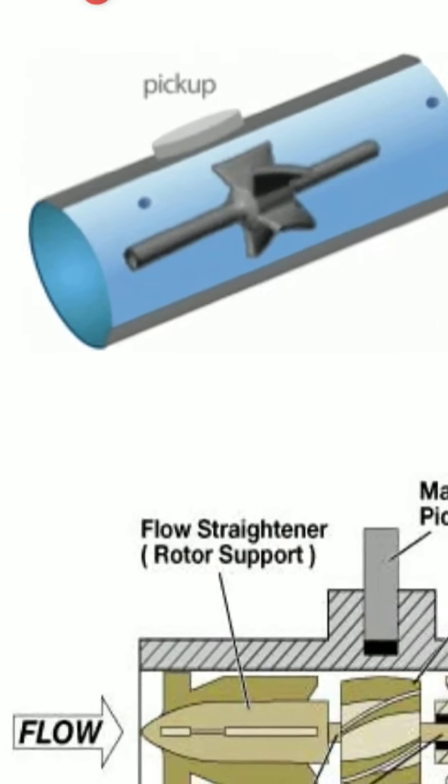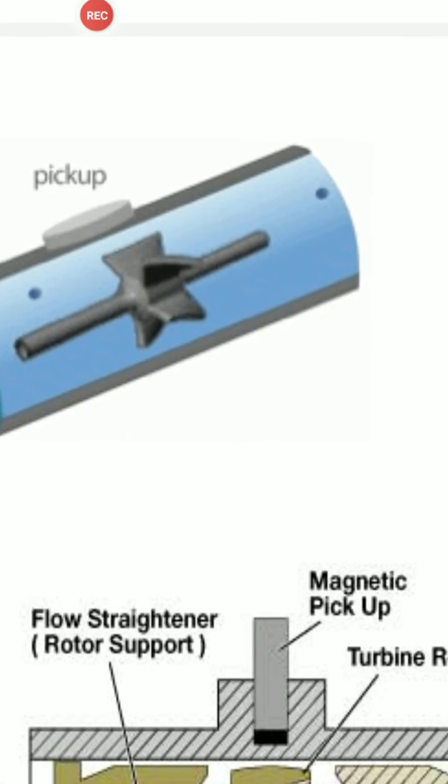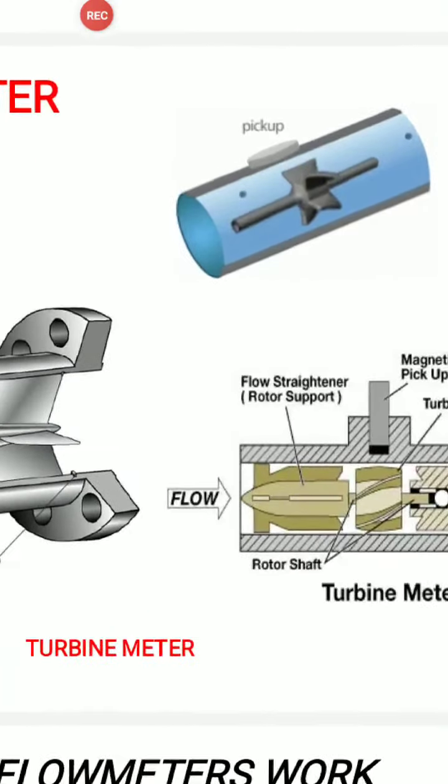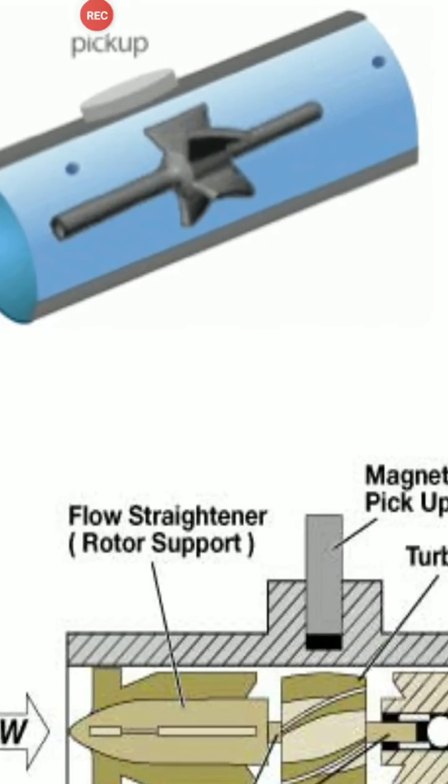The first sketch shows the pipe on the outer side, and inside the pipe there is a shaft with some blades fitted, called the rotor, and a bearing is fitted. Simple principle: when the water moves over the blades, as these blades have a particular design, from inlet to outer section of the blades, the fluid imparts its energy to the runner blades and it starts spinning around the axis, or starts rotating.